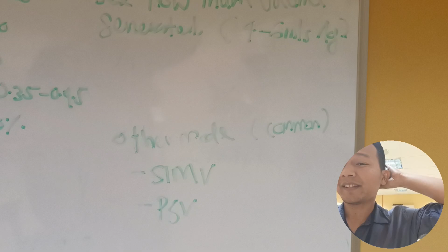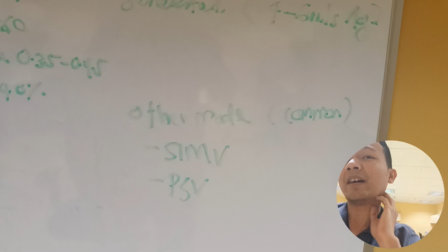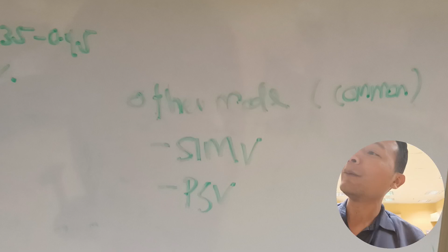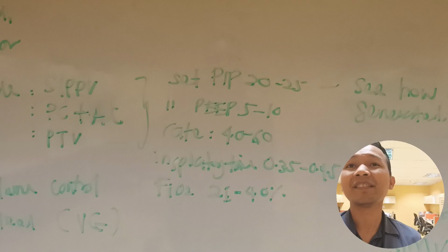SIMV is synchronous intermittent mandatory ventilation. So basically the machine will give only as many breaths as you set. For example, if you set SIMV at 30, the machine will give 30 according to this I time. Okay, if the patient breathes 40, the other 10 the patient breathes on their own with their own inspiratory time. The inspiratory time the patient sets themselves, while this one is set by the machine. So that's basically the main difference.